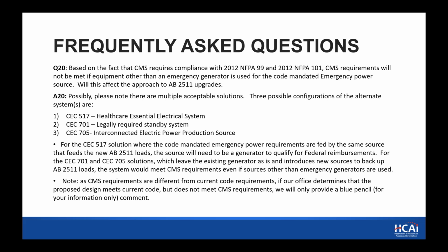So we talked about the 517 solution, the 701, or the 705. For the 517 solution, where the code mandated emergency power requirements are fed by the same source that feeds the AB 2511 loads, the source will need to be a generator to qualify for federal reimbursements. For the CEC 701, where it's just a separate generator picking up the transferred cooling loads, or CEC 705, where you have a microgrid that parallels the normal, you would need to leave the existing generator as is and introduce the new sources to back up AB 2511. Those systems would meet CMS requirements, even if other sources than emergency generators are used.